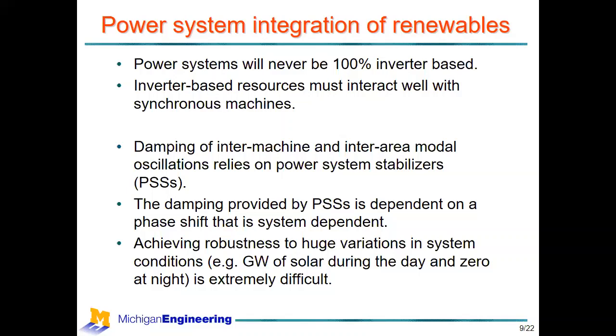The tuning of power system stabilizers, the damping provided from them, is dependent upon a phase shift that compensates for a phase lag through the grid. So the power system is actually part of the feedback process. And as that power system changes, the phase, or characteristics of the power system, change as well, making it very difficult to tune power system stabilizers across a wide range of network conditions.